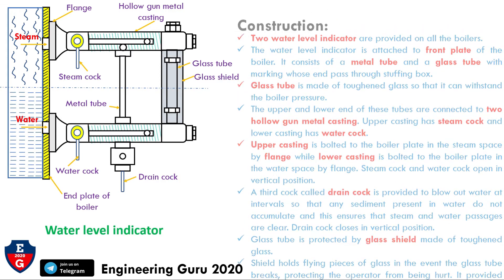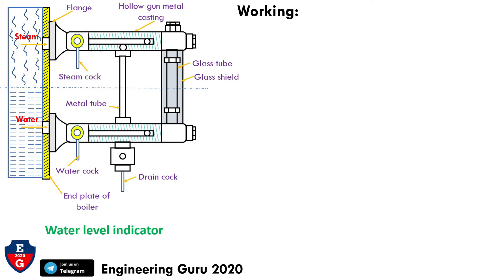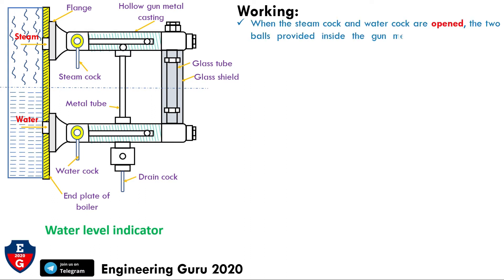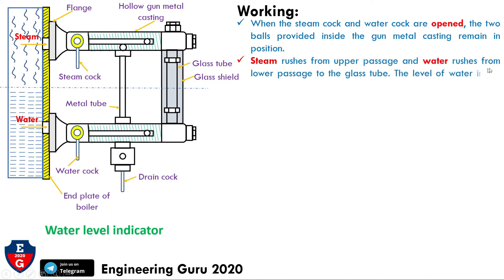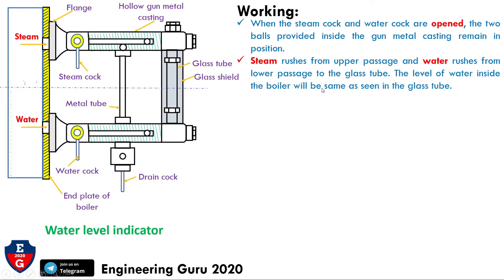Now for the working: when the steam cock and water cock are open — meaning they are in the vertical position — the two balls provided inside the gun metal casting remain in position. Steam rushes from the upper passage and water rushes from the lower passage into the glass tube. The water level inside the boiler will be the same as seen in the glass tube.